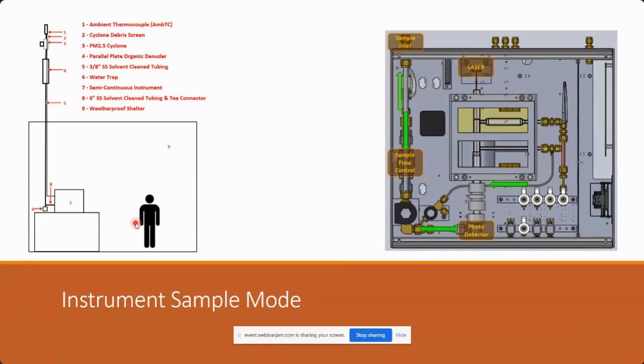For somebody wishing to set up one of these instruments, it would look similar to the schematic that I have up here, where it would typically sit in some sort of weatherproof shelter, anywhere from a large mobile room to a mobile collection laboratory. We've seen people put these in systems as small as a small cabinet.